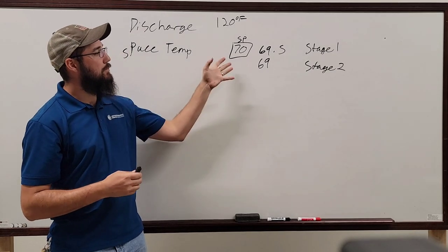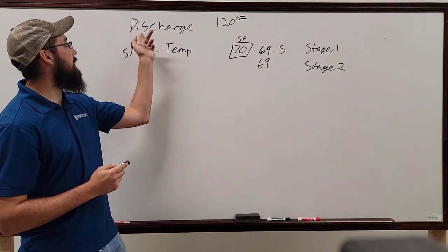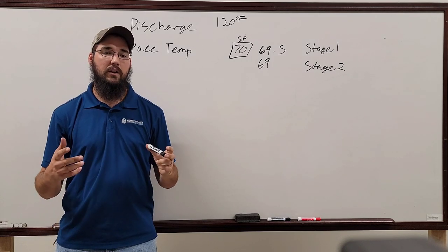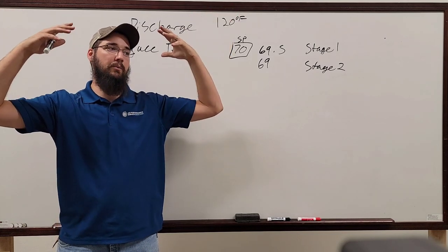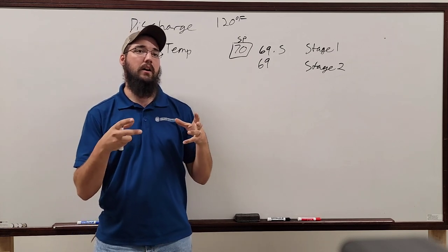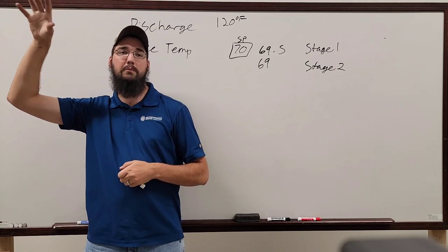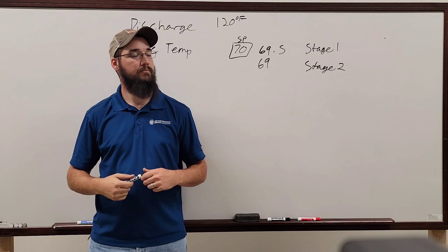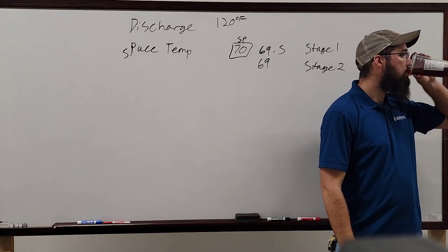Right. And this is pretty typical. A regular thermostat can accomplish this. A lot of automation systems will do this. You will see it control discharge air if it's dealing with a system that runs specifically on discharge air. So if we had an air handler with a bunch of VAVs and we went into a heat mode at that air handler, if it had the capacity, whether it be a hot water coil or electric heat strip, that air handler will then stage the heat to keep the discharge air at a certain temperature so that the boxes are getting fed the temperature we want. If it's a bigger handler with heating capacity, would they typically just be VAVs then and not fan power boxes?